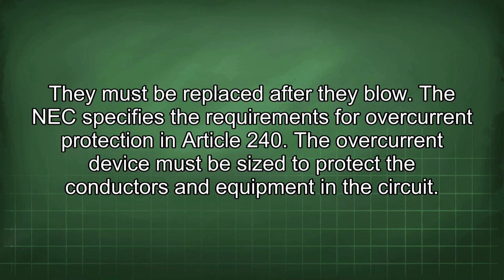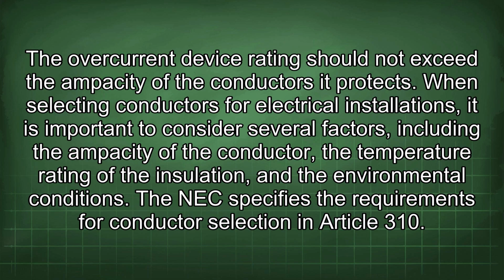The NEC specifies the requirements for overcurrent protection in Article 240. The overcurrent device must be sized to protect the conductors and equipment in the circuit. The overcurrent device rating should not exceed the ampacity of the conductors it protects. When selecting conductors for electrical installations, it is important to consider several factors, including the ampacity of the conductor, the temperature rating of the insulation, and the environmental conditions.